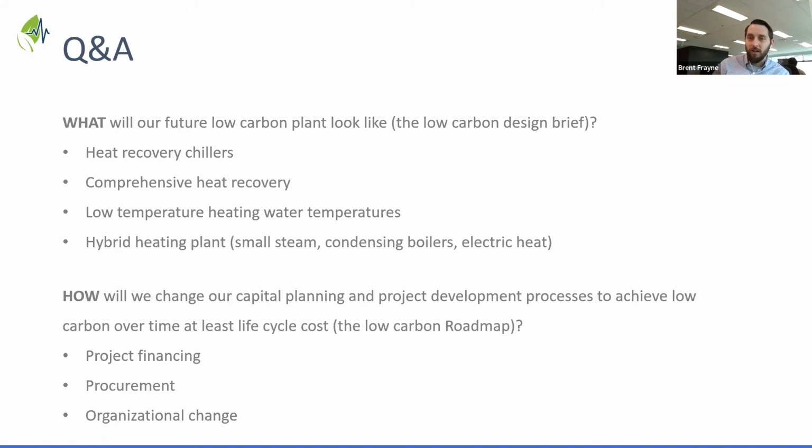It's a no-brainer to have air-to-air heat recovery in new facilities, but you'll look for other places, right? You talked about exhaust air streams that we don't have outside air running through, but can you suck heat out of those exhaust streams before they leave the building? Certainly you can, and you can put in pretty reasonably large coils. We're looking at it on some facilities to get quite a lot of heat out of those exhaust streams, right? If you can really subcool some of that air, you can really start to supplement the heating demand of the building and really start to reduce the demands that you put on that geothermal field.